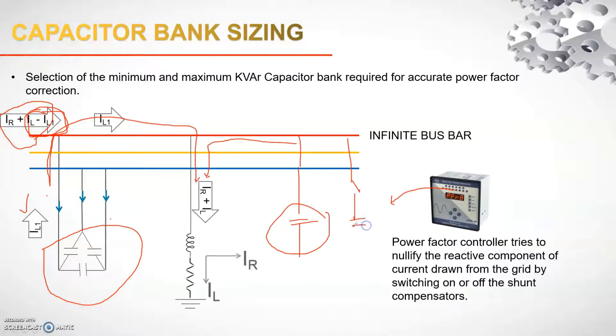Since we need multiple capacitor banks connected through switches to the bus bar, we need to understand what minimum and maximum values of capacitor bank are required. We cannot blindly connect any size — connecting one KVAR, two KVAR would be an economically huge loss. Hence a mathematical calculation is required.